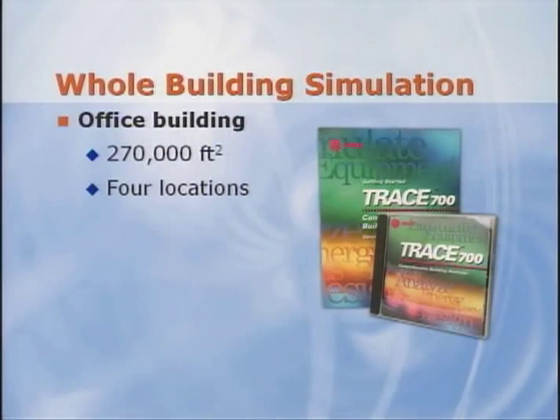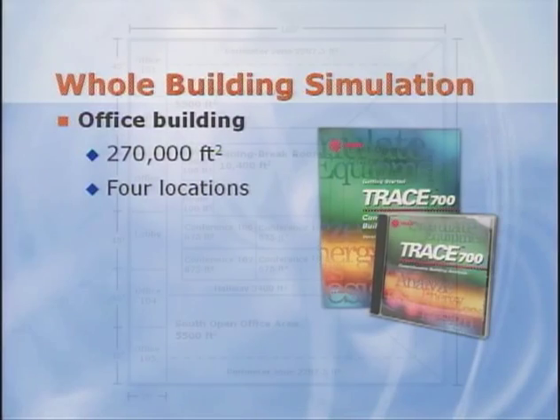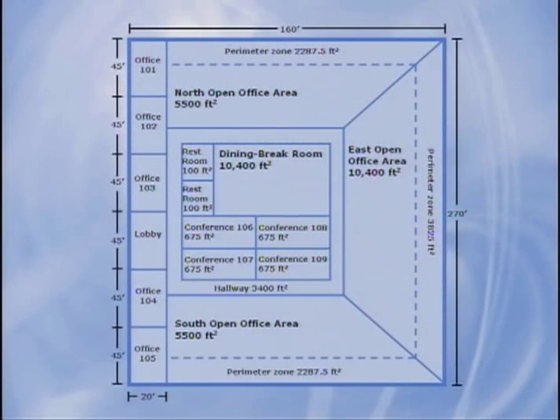Sure, John. We used Trane's Trace 700 building analysis software to model an example 270,000 square foot office building. As required by LEED NC, the baseline building was modeled according to Appendix G of ASHRAE 90.1, with 25% of the baseline building energy cost attributed to plug loads. For a building of this size, Appendix G requires the baseline to be a chilled-water VAV system. The energy rates used for this study were the state average prices that are published by the Energy Information Administration.